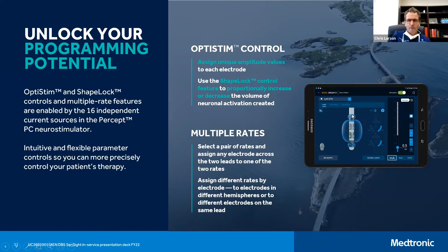And then this whole shape lock control feature, instead of giving technical control of the programming to the patients, creates a more user-friendly ability, and it allows folks not to get too crazy with their programming. They're able to modify some of their programming depending on their situation in a way that is confined to parameters, so that you don't push things too far and end up misprogramming yourself. But there's a big deal in these multiple rates, that you can program the rate and assign that to any of those independent four electrodes or contacts. So not just a directional thing, there's also a big deal in being able to tailor each of those independent electrodes, and not just create a stimulation out of one or between one or two at a constant rate.